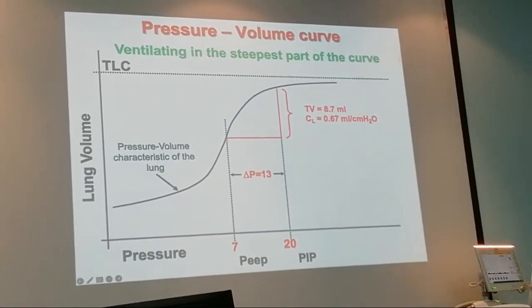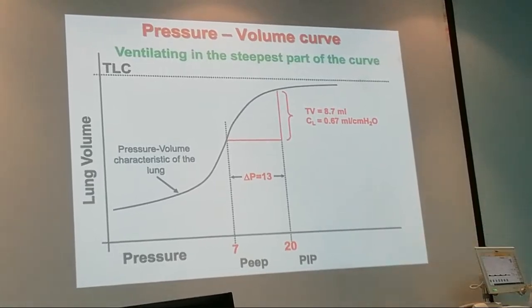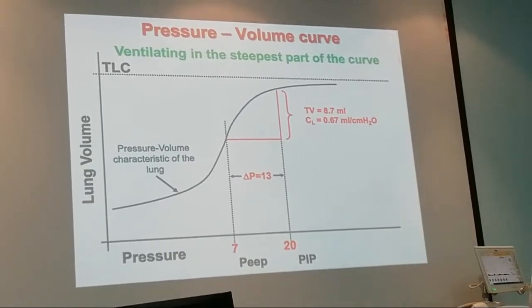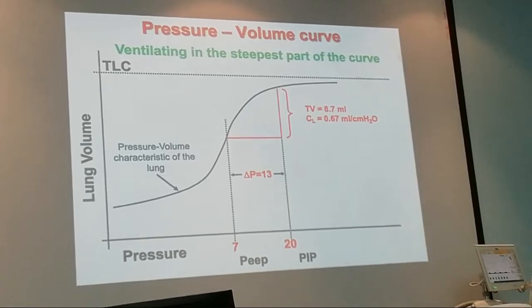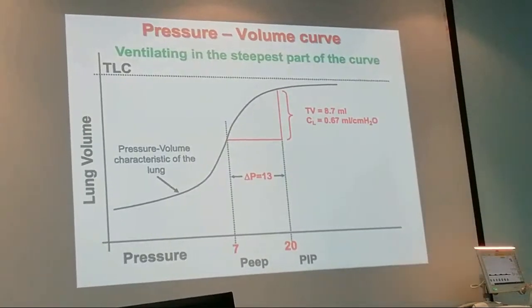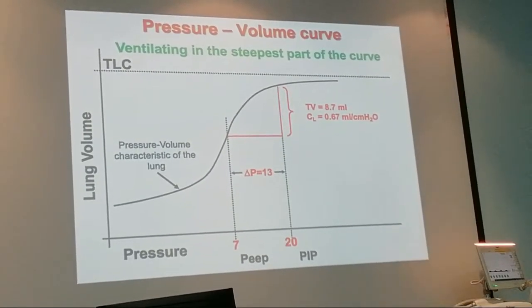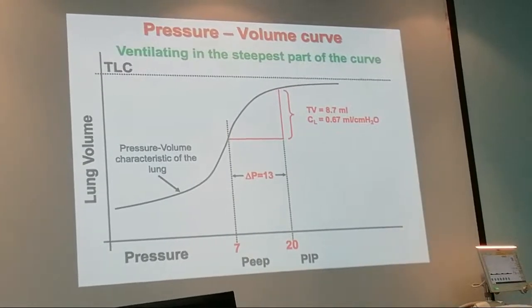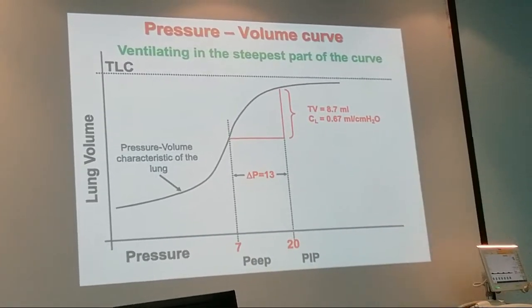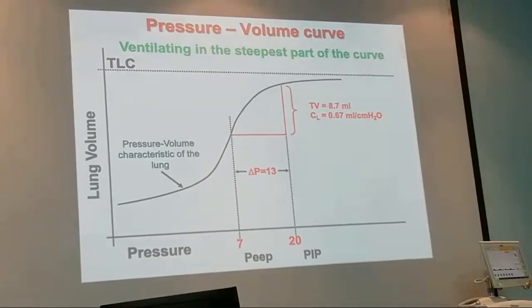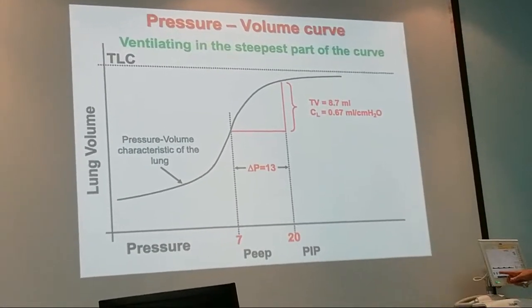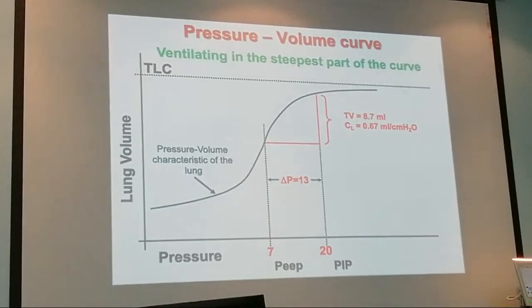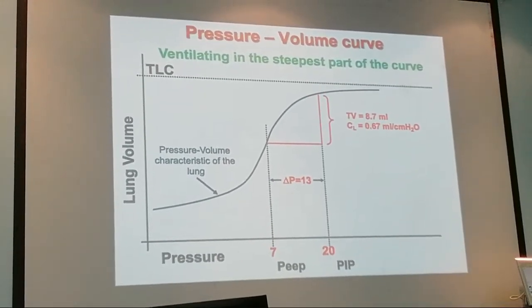is still 8.7, which is the same as before, but now the compliance is 0.67 because your delta P significantly decreased. So before, you needed almost the same volume with a much higher delta P. Now with significantly less delta P, you're almost achieving the same volume. Okay? Follow? So that's why it's important to know exactly where you are, in which part of the curve. And the machine will be able to tell you that.